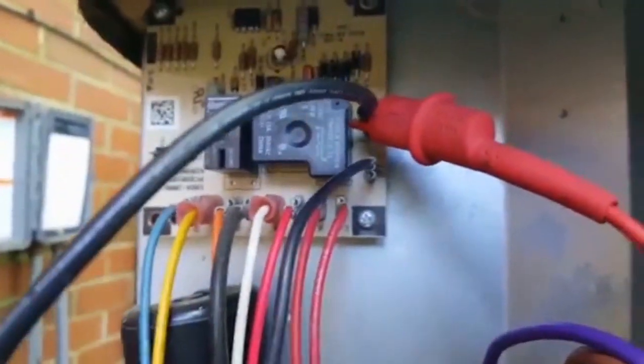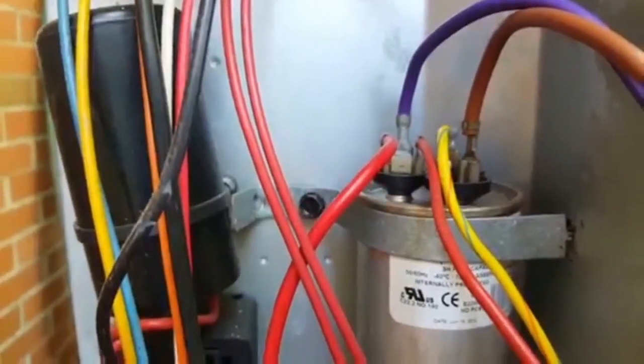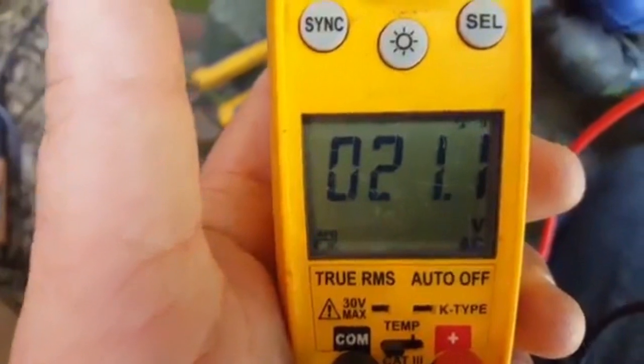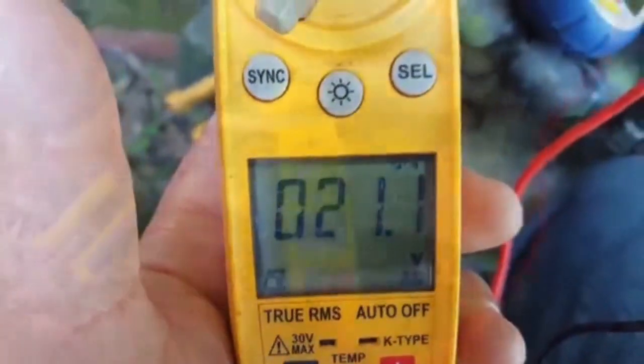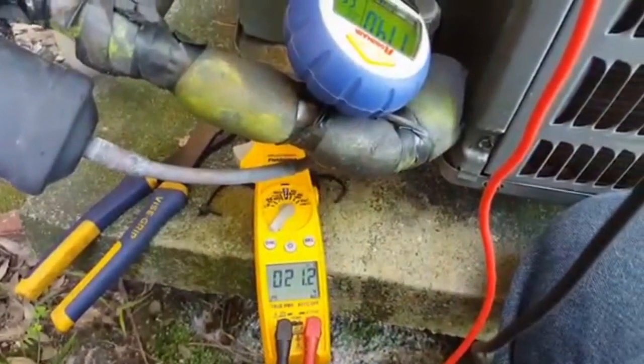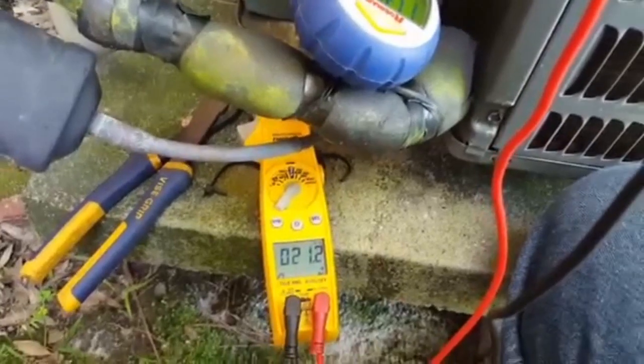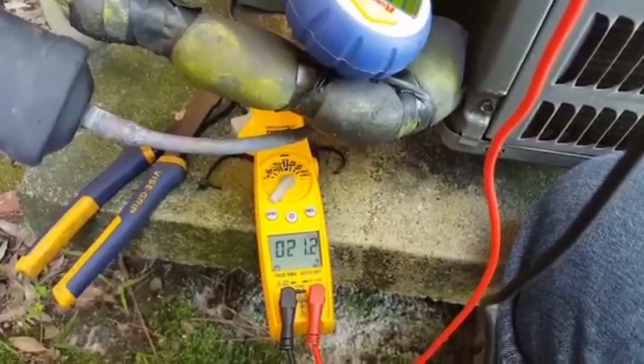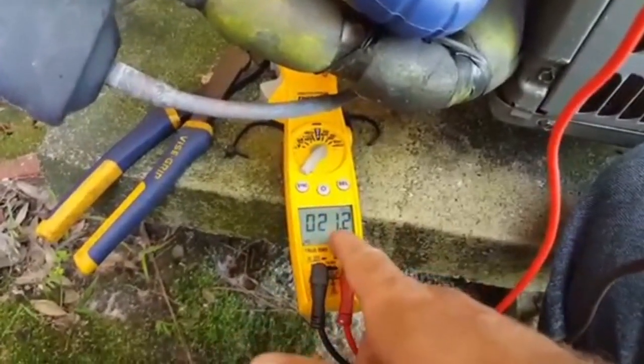21 volts from the defrost board to the common on the capacitor, which is the run winding. So from common to run, 21 volts. So it's trying to run. We have 21 volts, perhaps coming from a high resistance across the fan motor. I'm not sure, this is kind of an interesting situation.